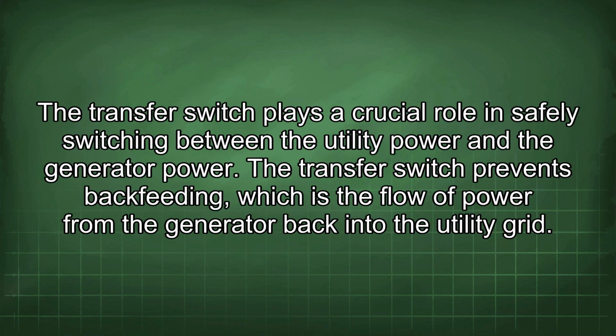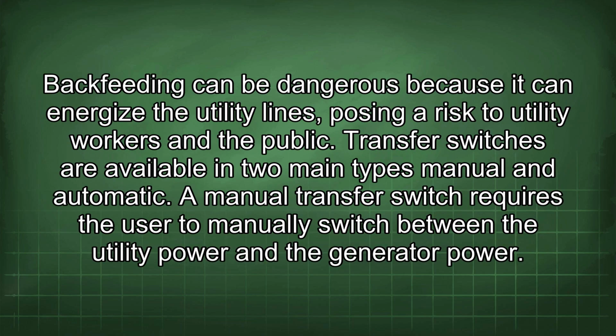The transfer switch plays a crucial role in safely switching between the utility power and the generator power. The transfer switch prevents backfeeding, which is the flow of power from the generator back into the utility grid. Backfeeding can be dangerous because it can energize the utility lines, posing a risk to utility workers and the public.